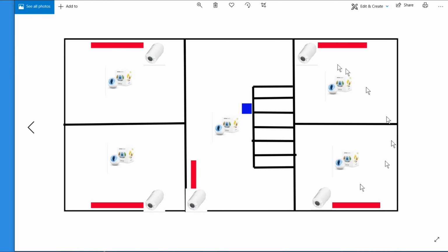So this is our typical house again. We get rid of the thermostat, which I forgot to remove from my picture. And what we do is we've got these motion sensors, multi-sensors I should call them, in every room anyway, as part of my alarm system. But not only do they do motion, they also do temperature. We then add in Z-wave TRV valves to each radiator. So rather than manual, we can now have full control over them as well.